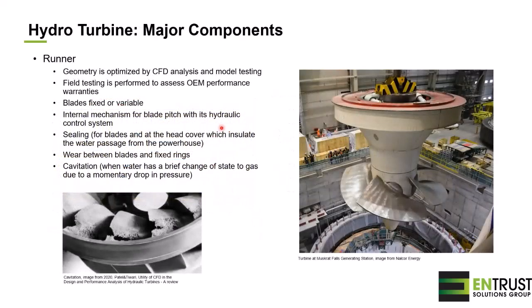If we look at the major components of a turbine, we'll find for sure the runner. The geometry is optimized by CFD analysis and model testing. From the model testing, the OEM will create a runner that will be put into a project, and at the end of the project they will achieve field testing. And for that, it's important to meet the warranties expected by the owner. We can have, as mentioned, fixed or variable blades. We can find an internal mechanism for blade pitch that will be controlled by a hydraulic system. Sealing is important for the blades here because it won't last forever. They will need to change that.